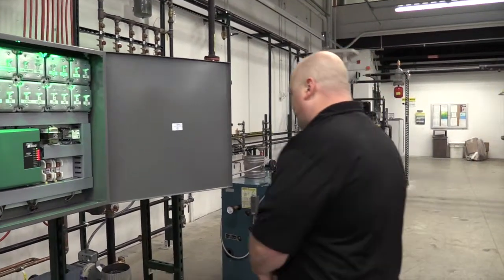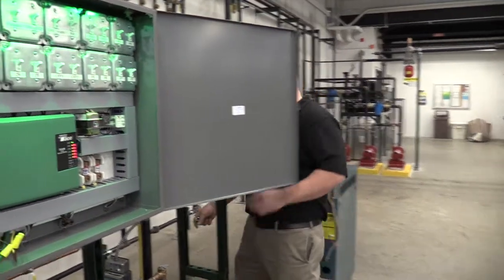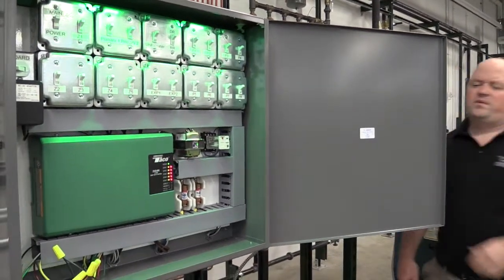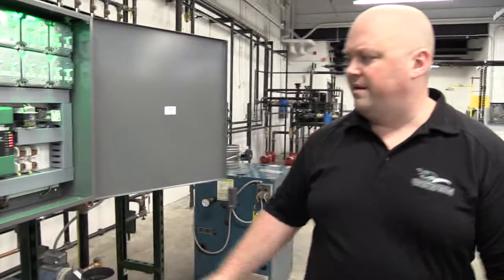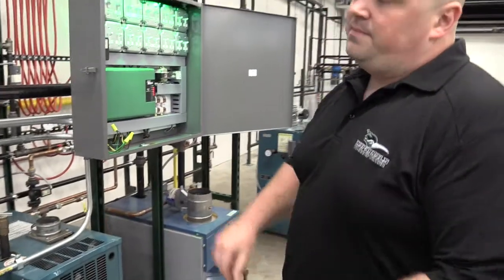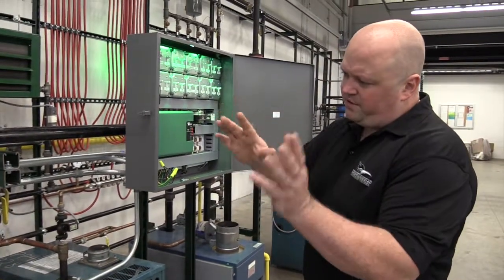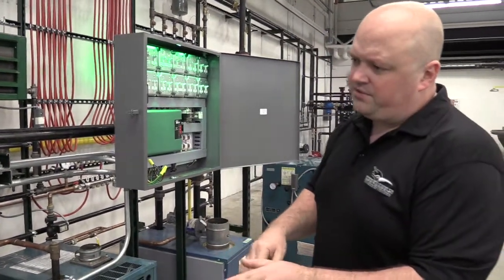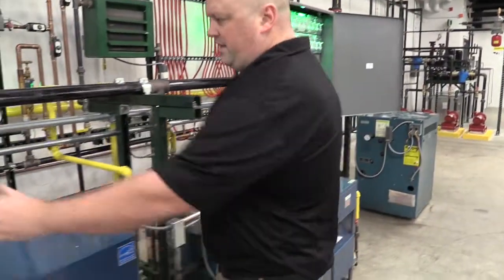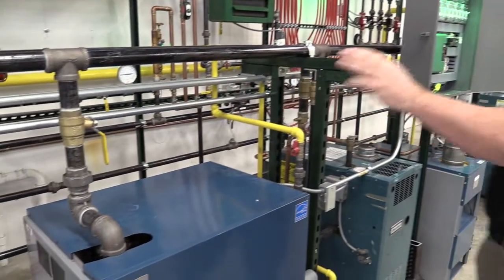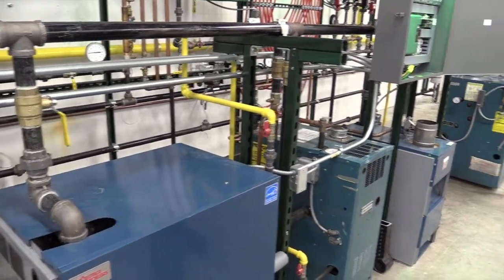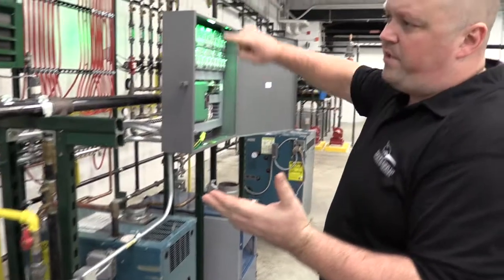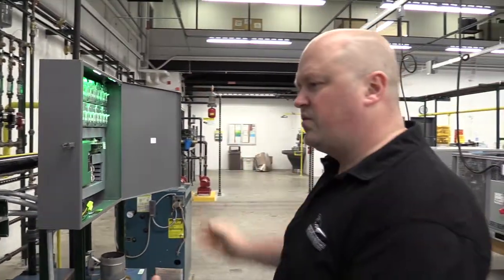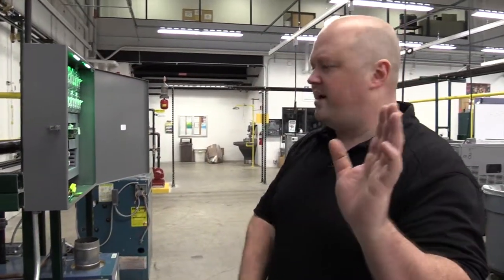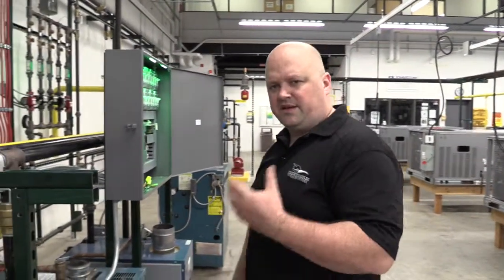We have a variable speed drive that will be on our main pump here, and you can watch the pump curve shift with system curves. Students have to come in and balance each one of these systems, put the whole system together how we want, and then evaluate and land their pump curves, then switch it into reverse return and change every different characteristic. So they really get to understand flow and balancing.